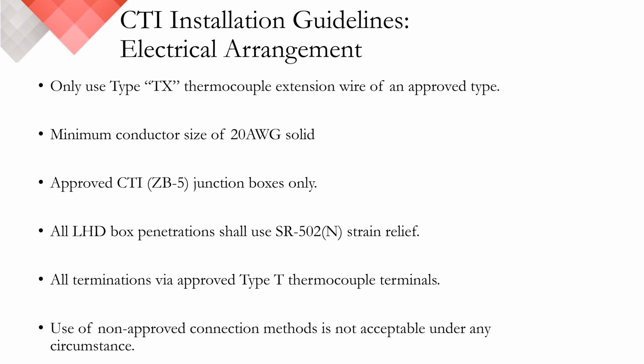With steel, we can reverse polarity, so to speak, and not impact the detector's ability to initiate. However, in a CTI series system, we can only use Type TX extension grade thermocouple wire as our feed cable. With the thermocouple, if we reverse polarity, we can induce what's referred to as a parasitic junction. Instead of reporting an accurate temperature profile, you can actually see information that starts ambient and then begins to jump as heat is applied. In most cases, these numbers will decline and show negative readings.